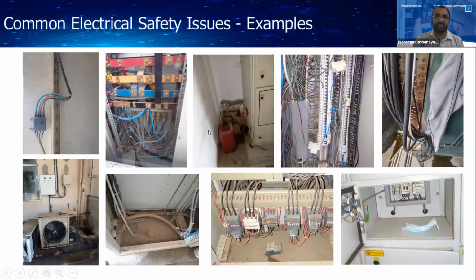This is the backside of an electrical panel. Here you can see the top ones, red, yellow and blue, are main conductors. Here you can see some small cables are taken out from this main bus bar. So there is no circuit breaker for these circuits. This main bus bar may have to handle 600 or 1000 amperes of current. But you have connected a 10 millimeter or 16 millimeter small wire directly to this bus bar to take power out. If a short circuit happens, definitely this will catch fire. So this is a very dangerous installation. Mostly, if you are visiting sites, you can see this kind of installation. Definitely in Sri Lanka, if you are visiting 10 sites, 6 sites are like this.